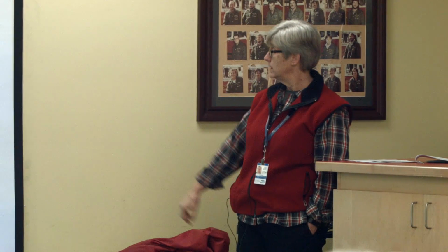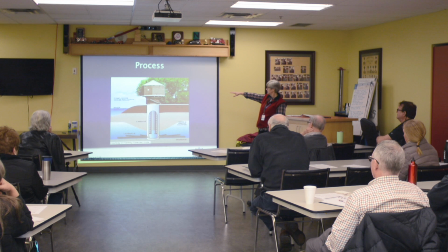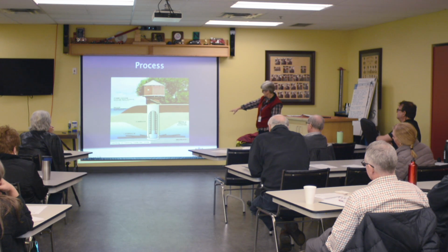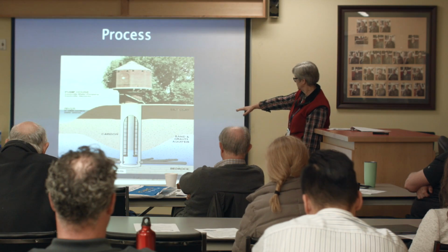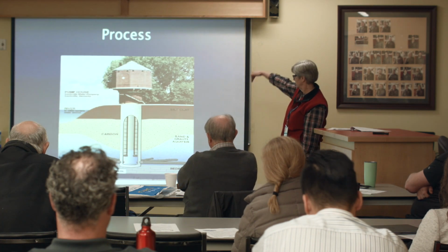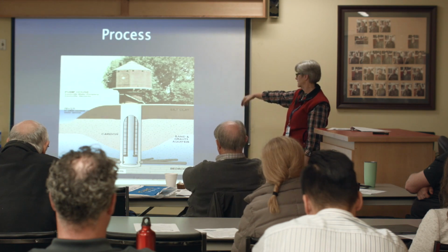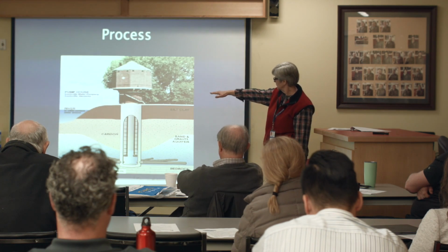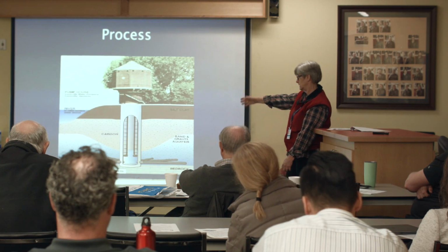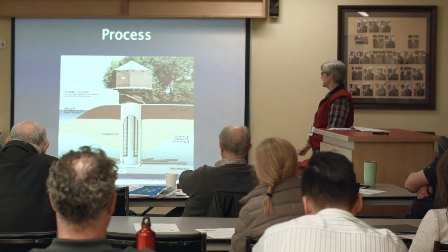Just a good example of your well beside a river. This is actually from Kentucky. You've got it elevated so that it doesn't flood. You've got the huge caisson, just a huge collection chamber. It's got the laterals going out on top of the bedrock. You've got your sand and gravel aquifers. You've got a silt layer, so silt and clay layer, so things coming in from the top aren't as likely to get through and down into it. But you've also got your river or other surface water source that may filter through the sands and gravels and get into your collection area and be taken up.